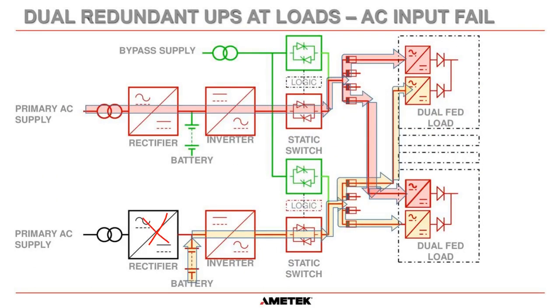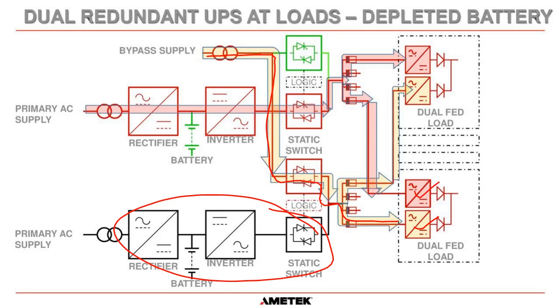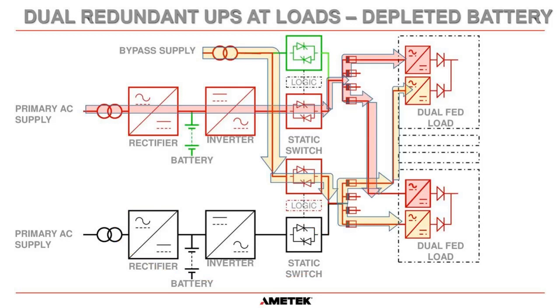If we have an AC input failure on one UPS, it will go to battery operation and both power supplies continue working. If the whole bottom UPS fails, it will switch to bypass, and you still have power going to both power supplies from the other UPS. You still have redundancy even if the UPS completely fails and transfers to bypass.